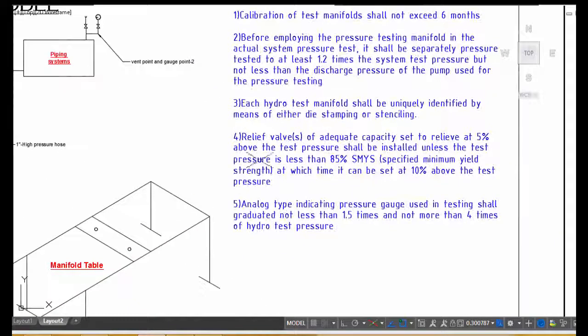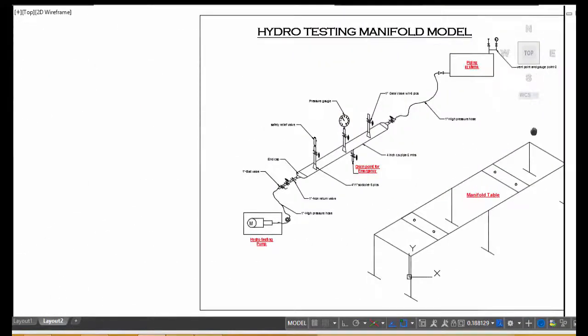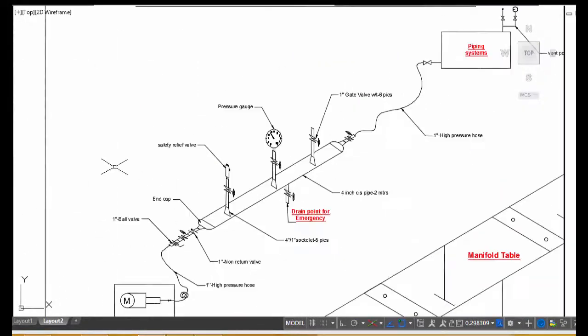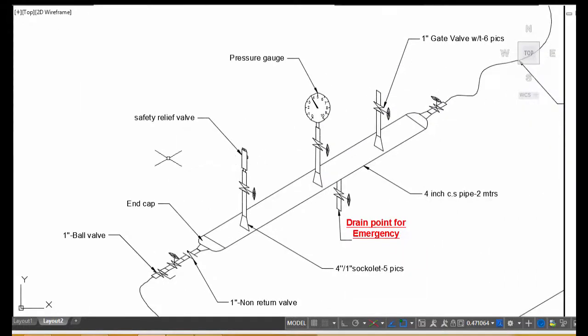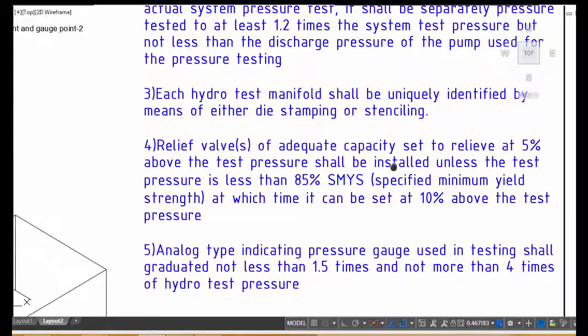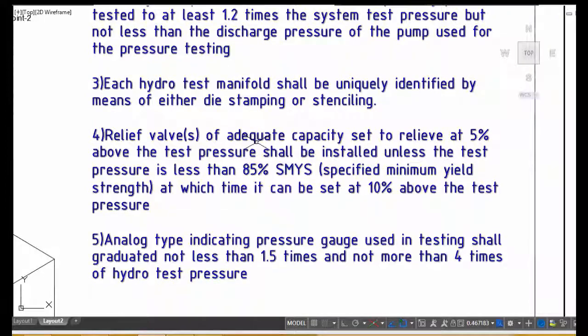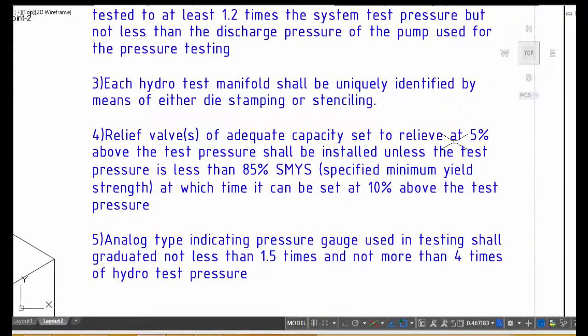And the relief valve - this relief valve should be 5 percentage above the hydrotesting pressure. Relief valve of adequate capacity set to relieve at 5% above the test pressure.